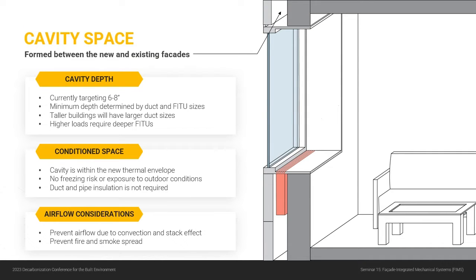So now we'll talk a bit about the cavity space. I mentioned typically targeting 6 to 8 inches. Obviously, you want it to be as narrow as possible, but you need to be able to fit your mechanical components. For the most part, if the building's not too big, you can probably keep it at 6 inches. But what's really determining the depth is the ductwork. So if you have a taller building and you need to carry more air in your ductwork, then the ductwork might have to be deeper. So you might have to go more towards 8 inches.